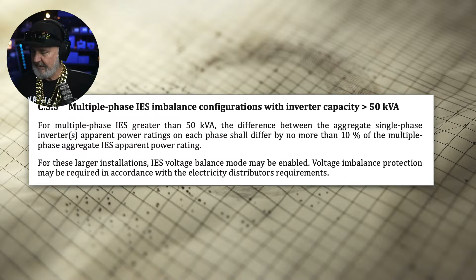And that means there are curious benefits of balancing. If you have a phase balanced system, you're actually required to export on phases that you'll not get any financial benefit from. You're not netting the sum of export and import in real time. You're getting credited for your export at a small rate and billed for your import at a higher rate at the same moment. So it's not netted. Therefore, it makes sense to put in a single-phase inverter on the most heavily loaded phase and maybe even avoid a three-phase configuration. It's a bit of an odd one. There might be other solutions for New Zealand, particularly once you add energy storage. You can move the energy around and achieve some other benefits.